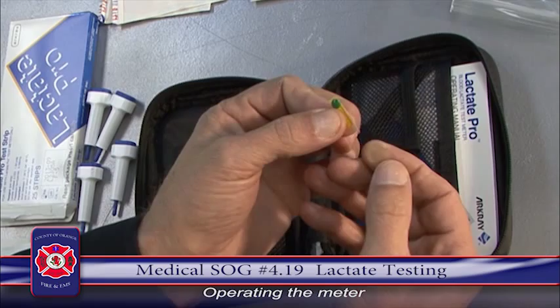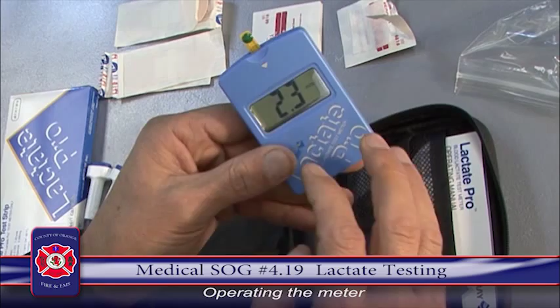You'll find a very small strip, and then you'll find in there the sticker that tells you what this should come out to be. So it's a check or test strip. So if this is functioning properly, we should have 2.1 to 2.6 millimoles per liter. And this is how this machine expresses it, 2.1 to 2.6. Other machines may express it as 19 to 23, and it may do it in an expression of milligrams per deciliter.